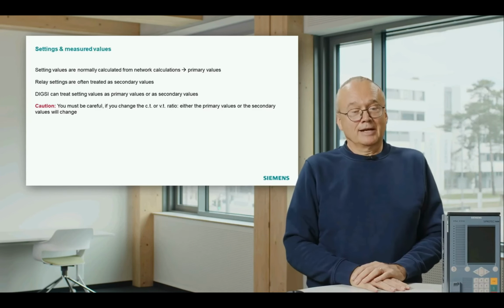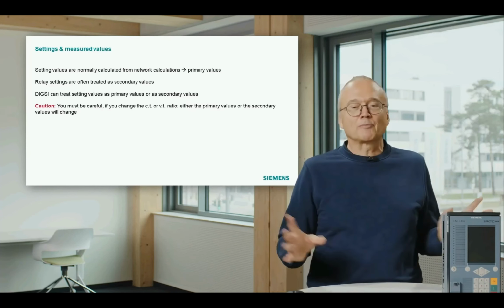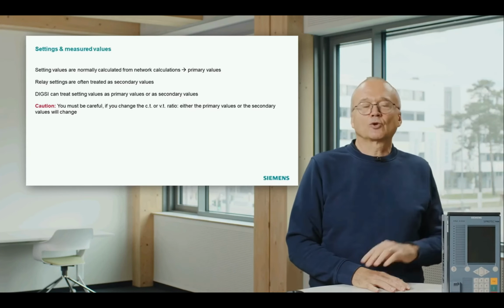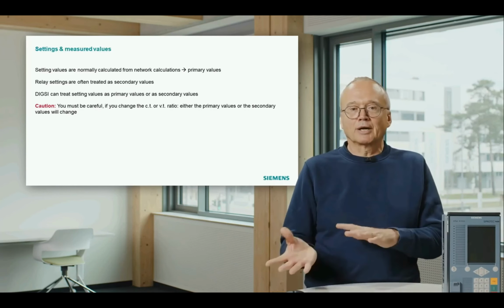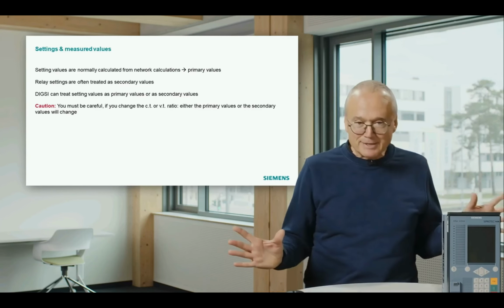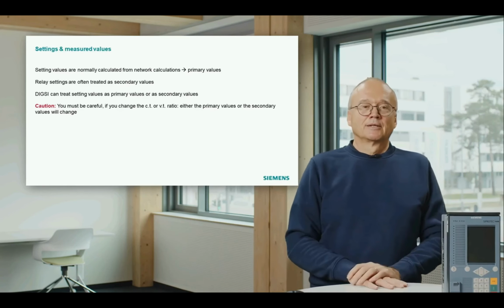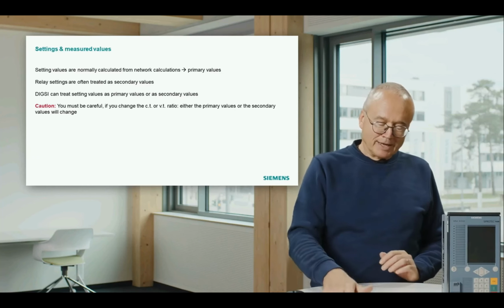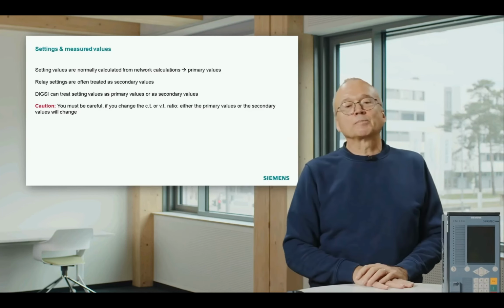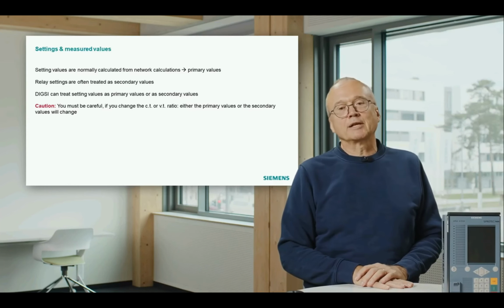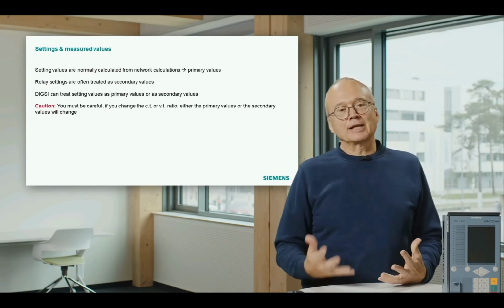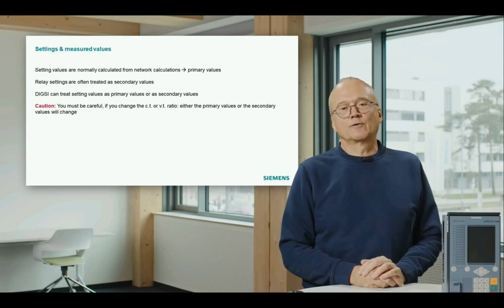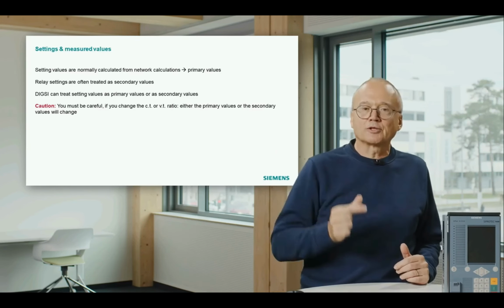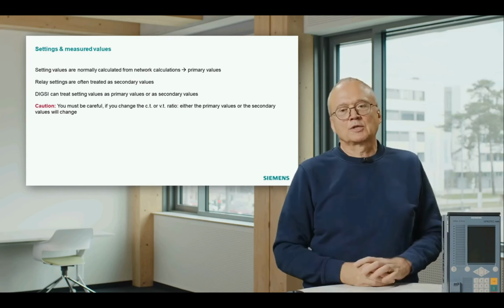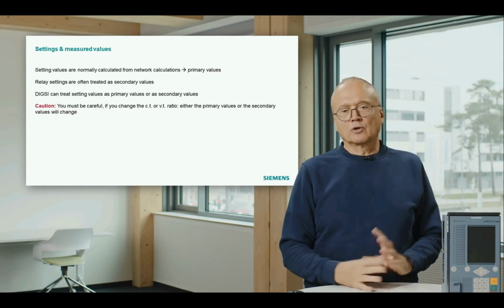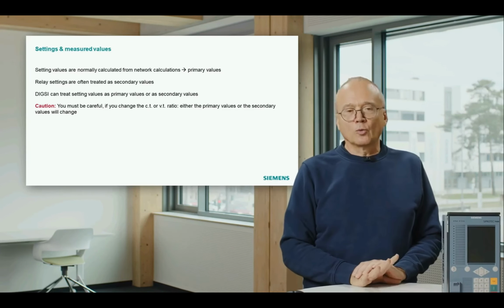And I had a lot of occurrences where something went wrong in the protection, and the end of the story was that people mixed up between primary and secondary values. It is basically trivial, but sometimes problems happen at that point. And the other thing, the other location where you have to be careful is the question, what is going to happen if a relay is in operation and somebody has the idea to change the current transformer? That means to install a current transformer with a different ratio. That can happen because something has to be replaced or the substation is extended or whatever.